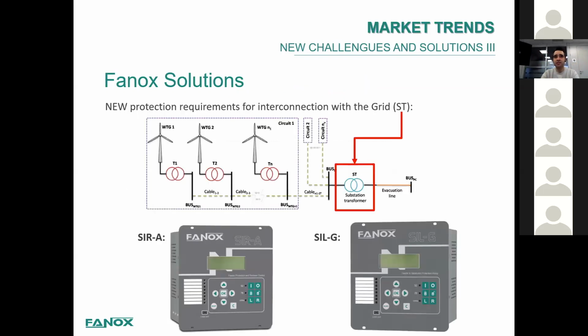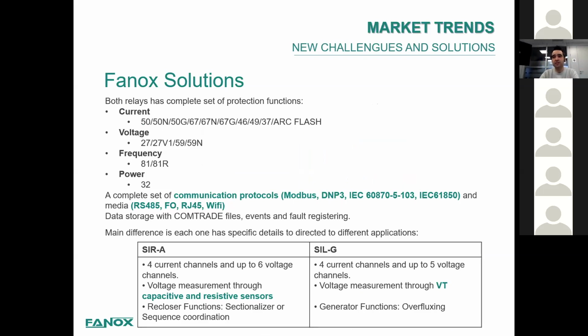For those impacts, Fanox has been taking a second step, with a more advanced restructuring of our relays, and we are working on the integration of these wind farms with the traditional grid lines, HV and MV. For that, we have these relays, that second generation of relays, SIR-A and SIL-G, that can work as these interconnection systems to the grids. Both relays have a complete set of protection functions: overcurrent, earth fault, with all the directional and undercurrent. We also have arc flash to detect the important.